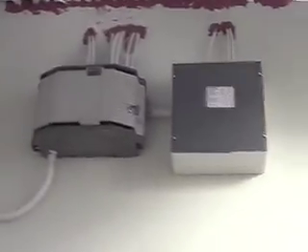The way that we powered all the VAVs is they all go back to a 500 VA transformer, which has individual 100 VA circuits, so it's still a class 2 circuit. Basically we run about 5 VAVs per 100 VA circuit, and so typically these will run about 25 boxes. They're spread throughout, and the locations of where they're at will be on the drawings.